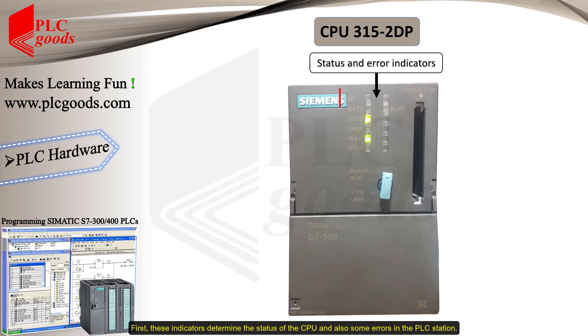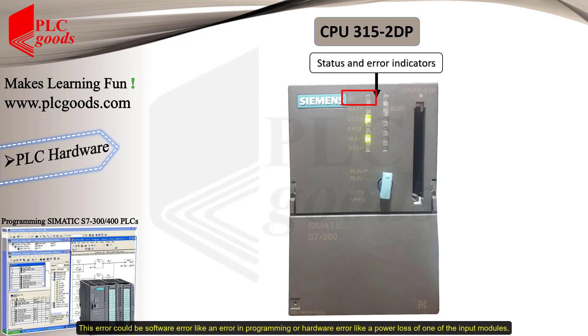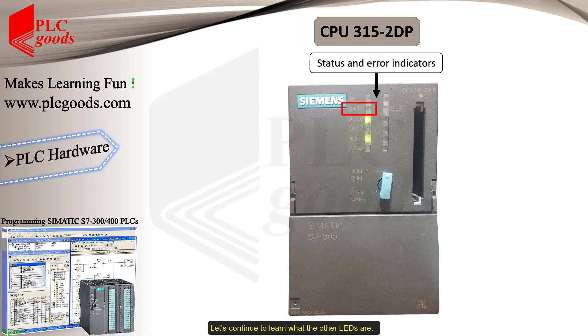Now let's learn about the different parts of the CPU. These indicators determine the status of the CPU and also any errors in the PLC station. On the right side, the BF (Bus Fault) LED indicates there is an error in the system network, such as a bad contact in one of the communication connectors or an address overlap in the network. On the left side, the first LED — SF or System Fault — indicates there is an error in the system, which could be a software error like a programming mistake, or a hardware error like a power loss on one of the input modules.